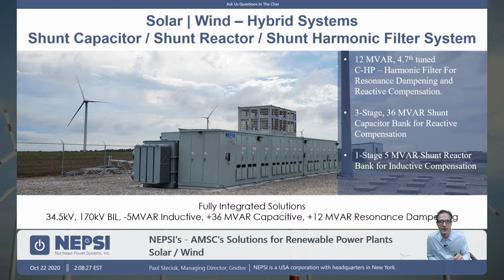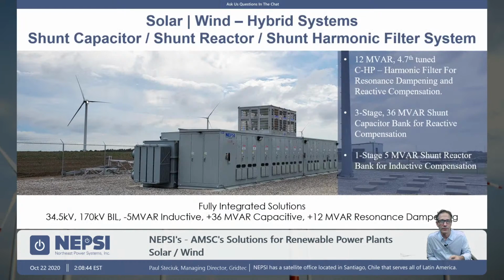Whenever you install a capacitor bank on a system, you are causing resonant conditions. When you have a wind farm with a lot of cable capacitance, you have resonance concerns. These turbines over here oftentimes are very good from a voltage and current distortion point of view, but typically they're putting out low levels of harmonic current distortion. Even low levels of harmonic current distortion, when injected into a resonant condition, can cause problems. So oftentimes wind farms and solar plants are plagued with this problem that they might have a resonance issue.